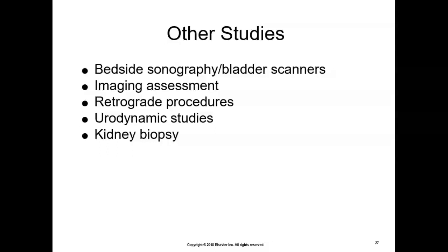Before scanning, you have to select either a male or female icon on the bladder scanner. What it really should have a picture of is a uterus, because that's what you're trying to figure out. If it's a female with a uterus, you would use the female icon. If it's a female without a uterus who's had a hysterectomy, or a male, then you would use the male icon.